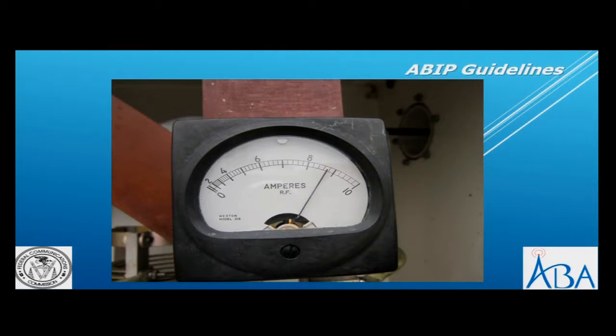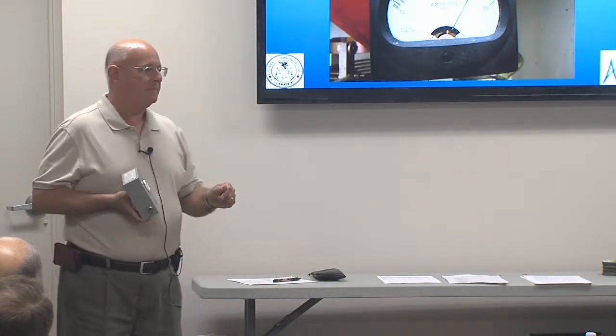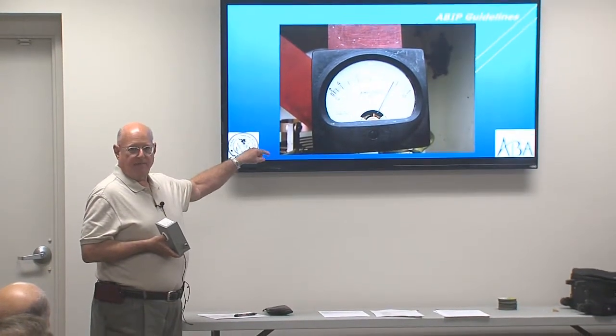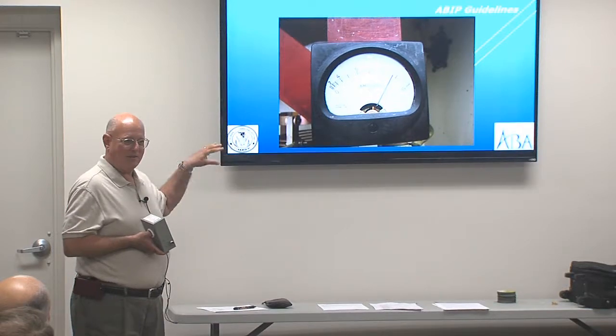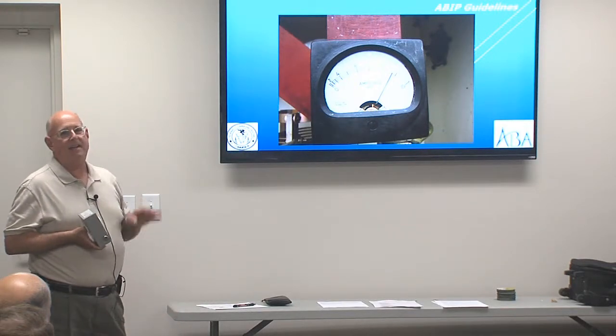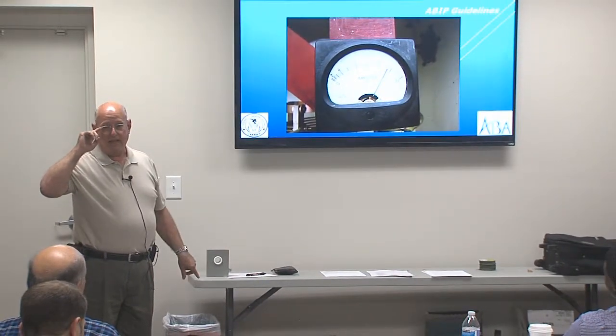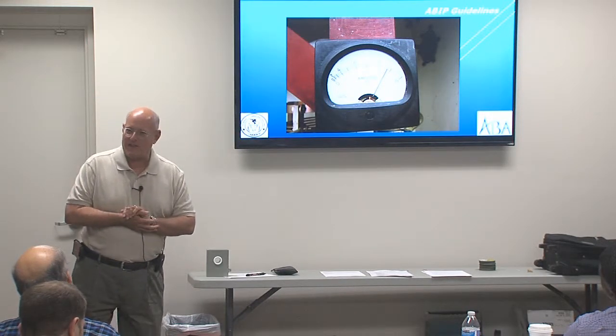You see these meters sometimes as plug-in meters. The way this works, there are dual jacks in the antenna tuning units. Usually there is a solid Bakelite jack and an empty jack in front. You plug the meter in and then pull the other jack out, so just this meter is reading and you get your amperage reading. Have the engineer do that because things do happen. I've seen people make errors and unplug one before they plug the other in, and it makes all kinds of pretty flames when that happens.